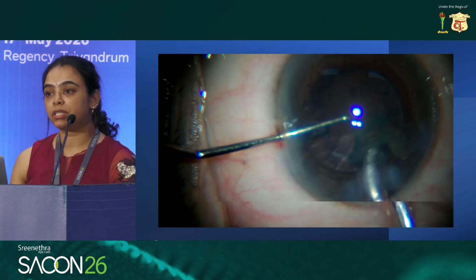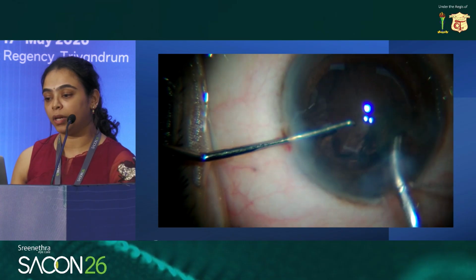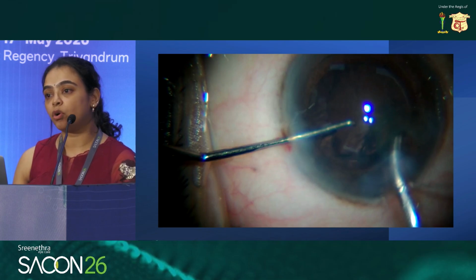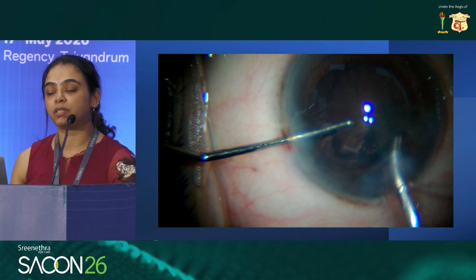Whenever there is excessive nucleus chatter, we should make sure that our phaco settings are adequate. For most cataracts, an efficient torsional phaco can be done effectively with high vacuum to reduce repulsion, with an optimum aspiration flow rate and with an energy of 60 to 65%.